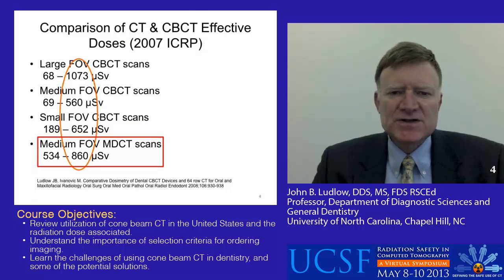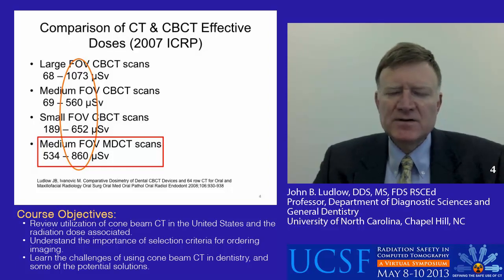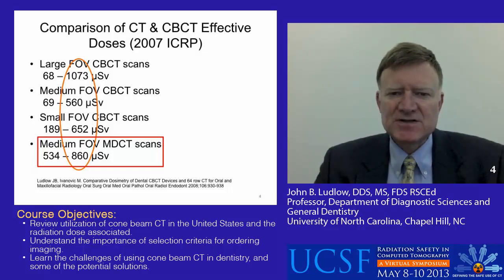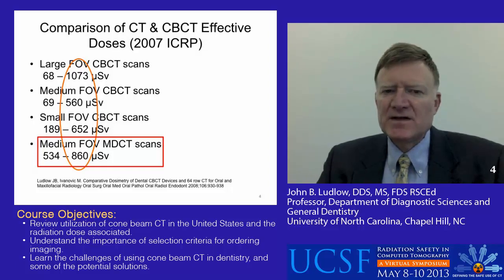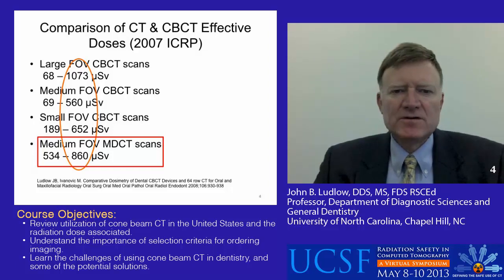Looking at the dosimetry of these different devices, when we divide them by rough volume sizes — small, medium, and large — and compare them with state-of-the-art MDCT dosimetry, we see that first there's a significant range of dose produced by these devices. Similar fields do not provide similar doses; these are dependent on other technical factors. But what we do see is that the high end of our dose ranges are comparable with doses encountered with state-of-the-art medical CT imaging.